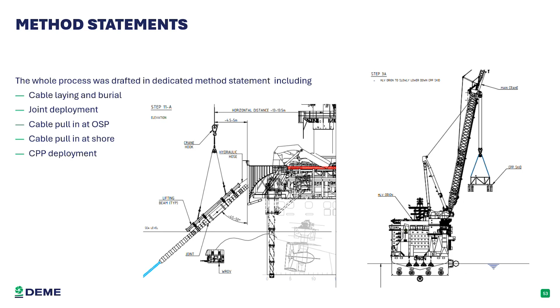As I was saying, the next phase was the verification of the burial of the cable and the installation, using software that is a common industry standard, OrcaFlex. Regarding installation, one parameter we think is important to highlight is that we believe these assets to be especially critical because of the amount of power carried. So a specific cable burial risk assessment shall be performed by project, but we forecasted that a higher depth of installation might be needed, and so this needs further attention.